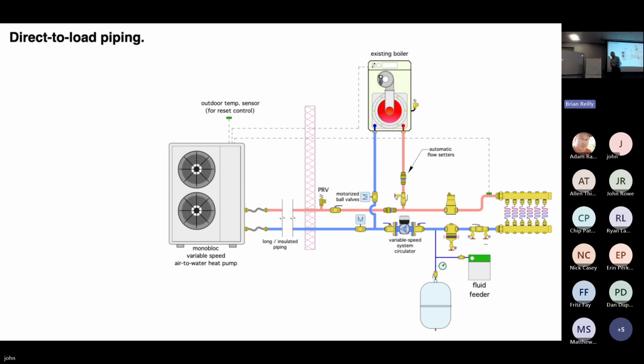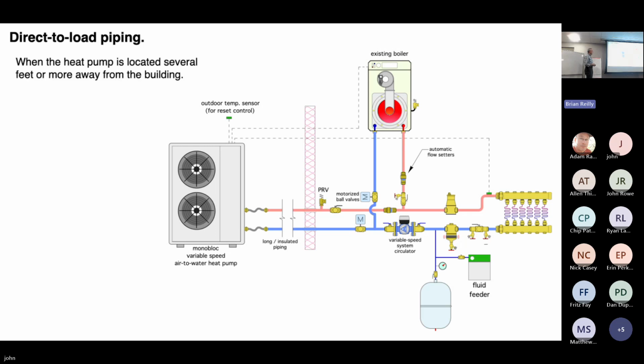In fact, all the monoblock heat pumps have flow sensors. And when a monoblock starts up, the first thing that turns on is the circulator, and it might run for a couple of minutes before the compressor turns on. It's doing that to verify that there's stable and adequate flow through the heat pump, because you don't want to turn on the refrigeration cycle if, let's say, the pump failed. This is telling the heat pump, the pump is working, I have adequate flow, I can start the compressor. So that's another approach.